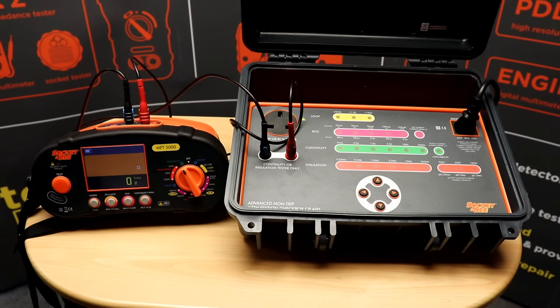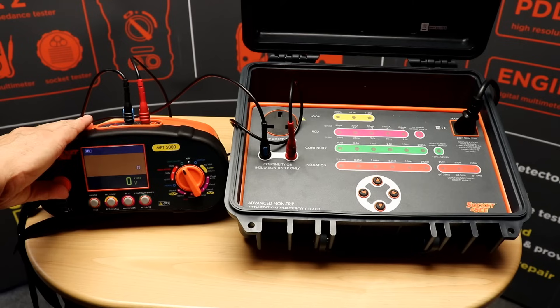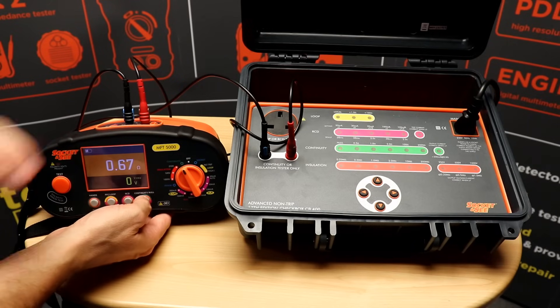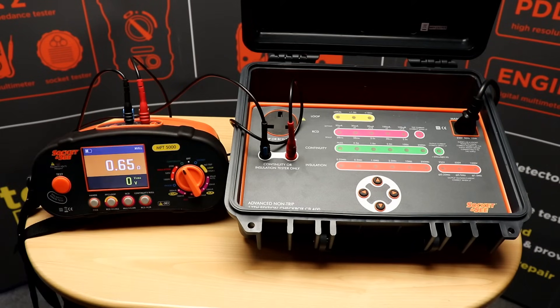Next we're going to check the accuracy of the continuity feature on the MFT 5000 using the Socket & See CB400 checkbox. If I press test while null is selected on the CB400, I get a reading of 0.67 ohms. This is the resistance of the test leads and the internals of the CB400. So now I will press continuity null to zero the measurement, so once reading zero I can then apply the resistance using the test box.